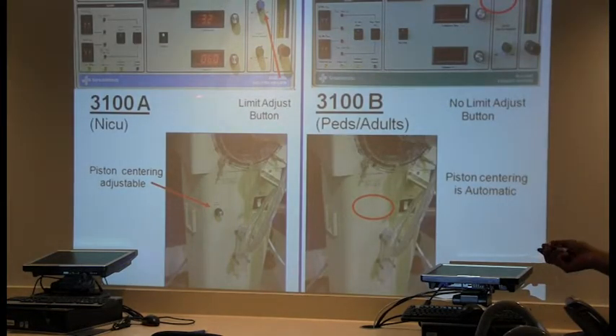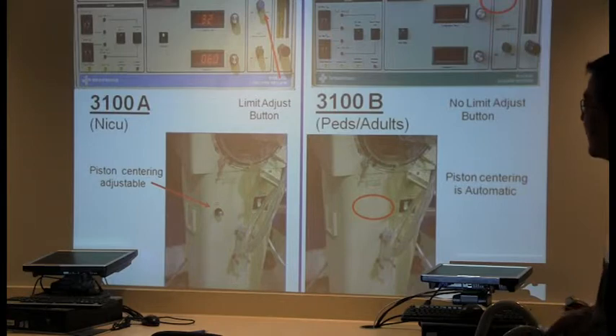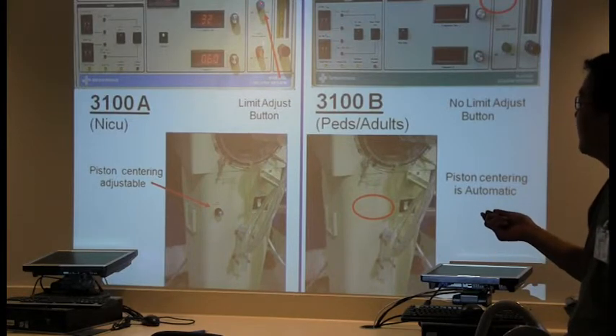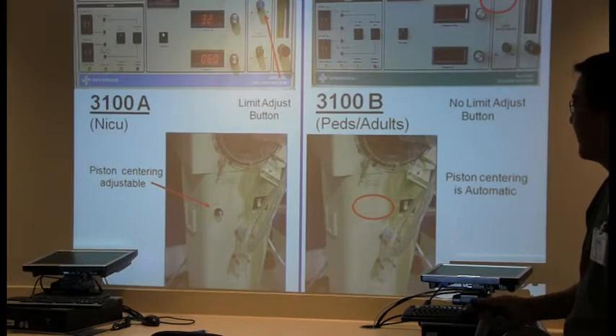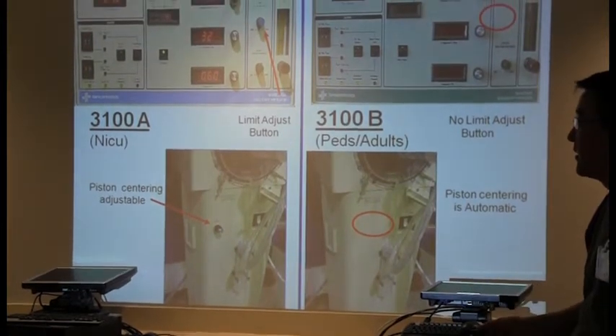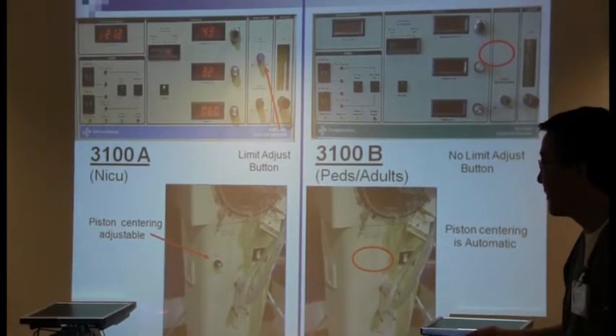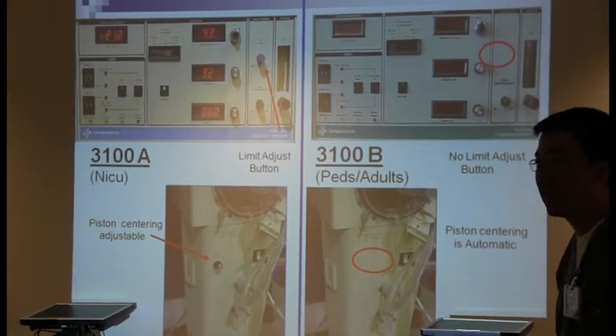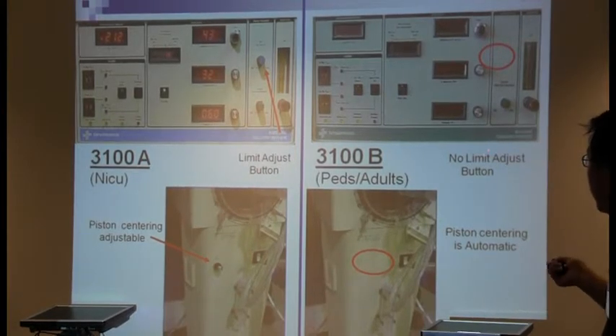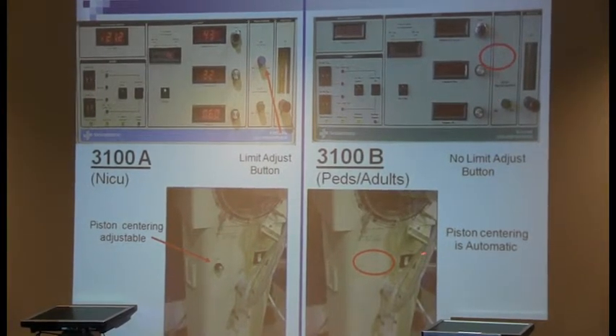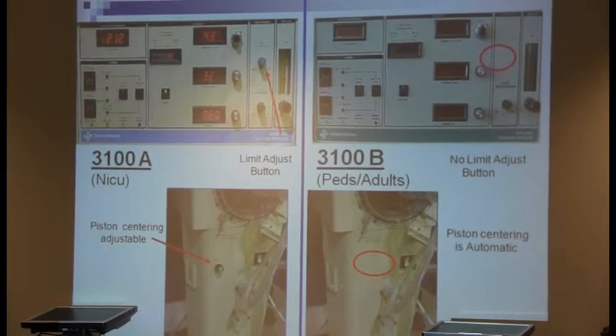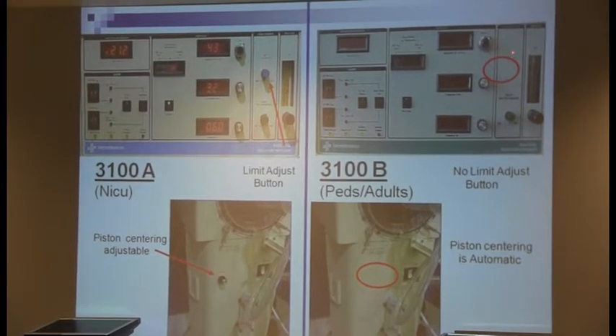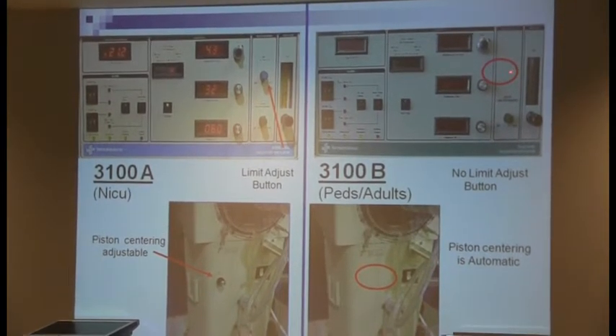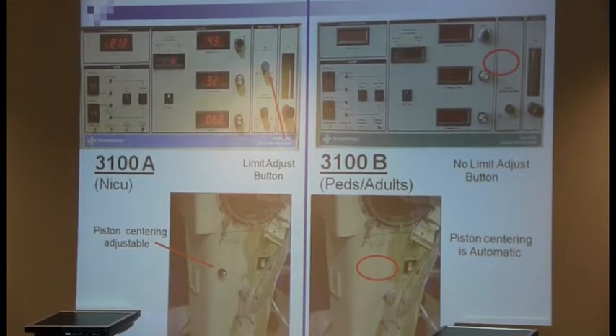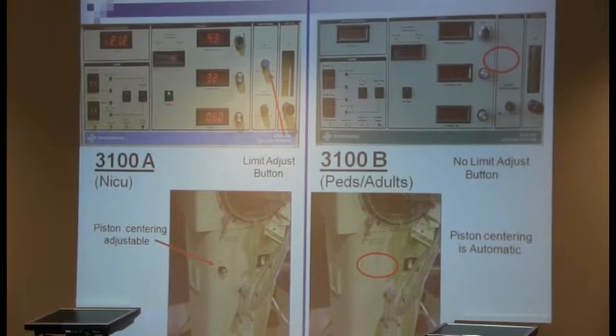Okay. So let's look at the difference between A and B. The A, we have two buttons here on our limit. And we also have this piston centering adjust, because the magnet's so small that we have to center the piston. The B, we have no piston centering. You don't have to worry about it. And if you look, you don't have this limit adjust button. You only have one button to adjust your mean.